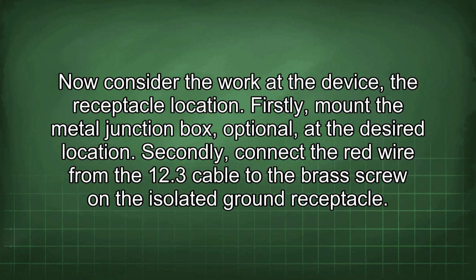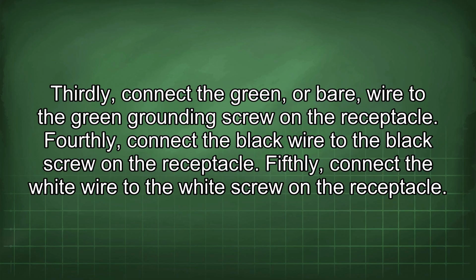Now consider the work at the device, the receptacle location. Firstly, mount the metal junction box, optional, at the desired location. Secondly, connect the red wire from the 12-3 cable to the brass screw on the isolated ground receptacle. Thirdly, connect the green, or bare, wire to the green grounding screw on the receptacle.